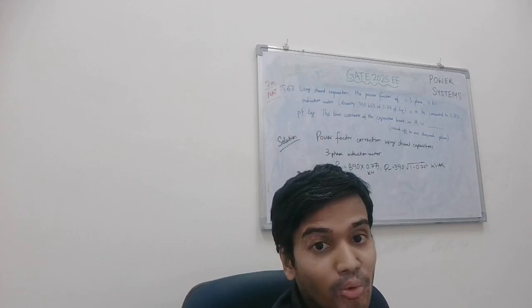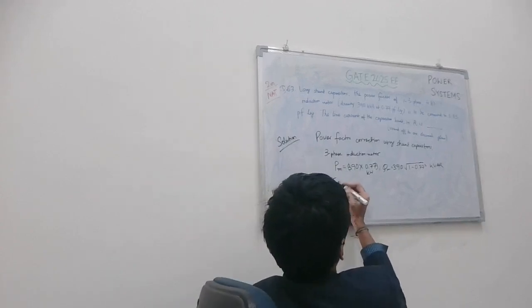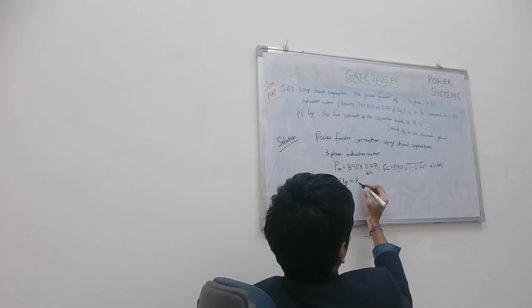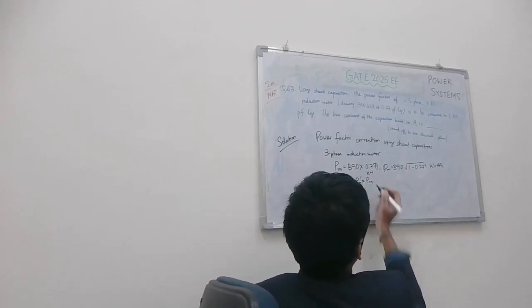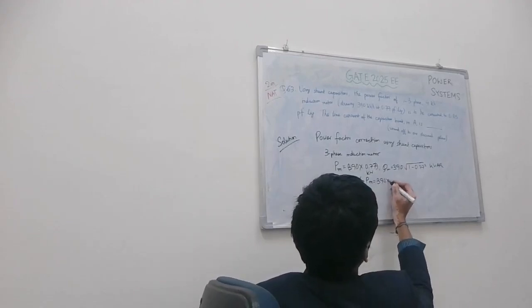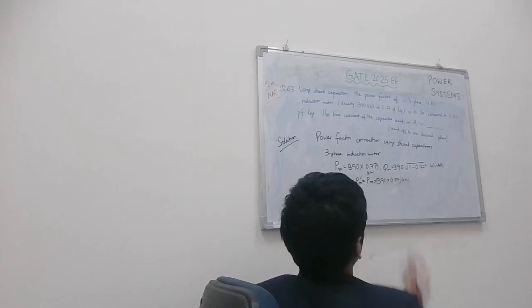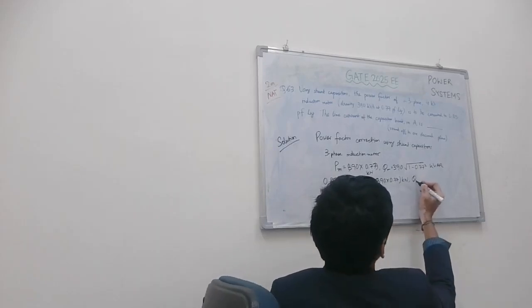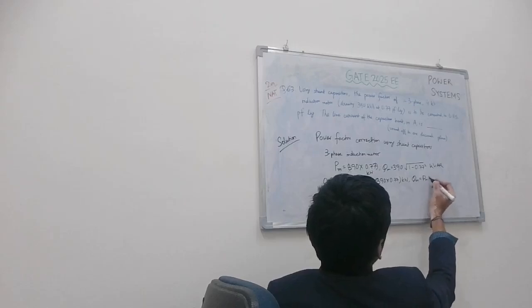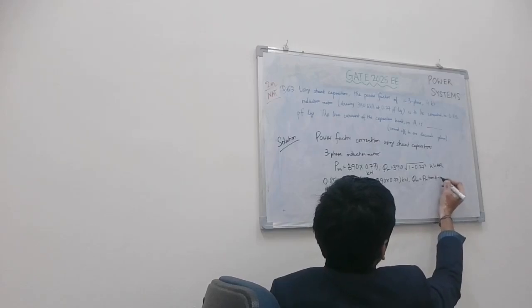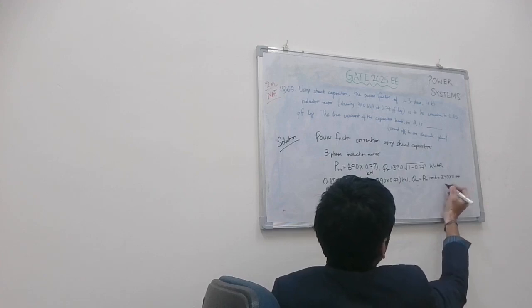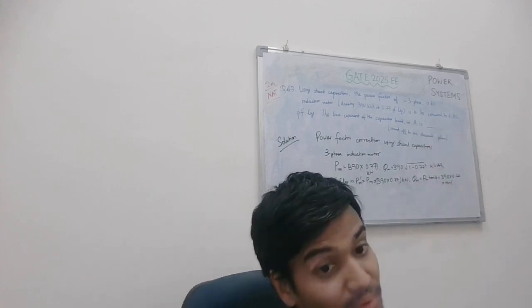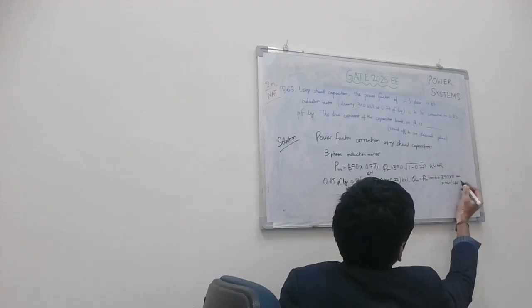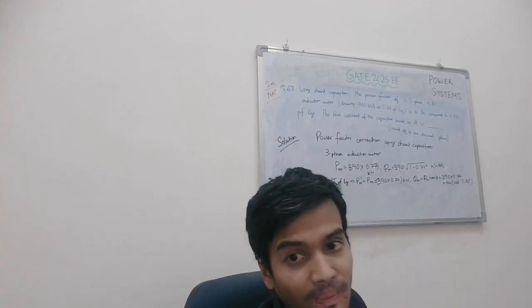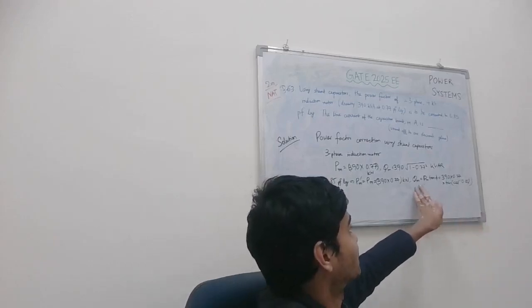Now to correct the power factor to 0.85, the new active power remains the same while the desired reactive power is calculated using the corrected power factor of 0.85, giving the desired reactive power of the motor.